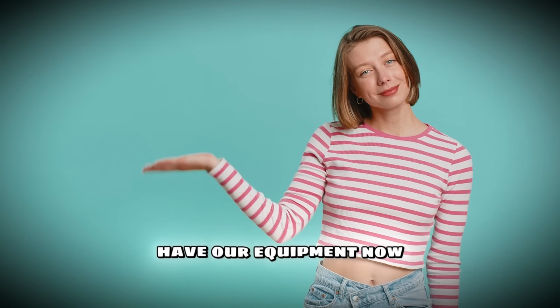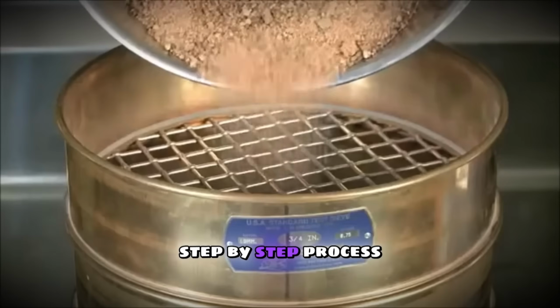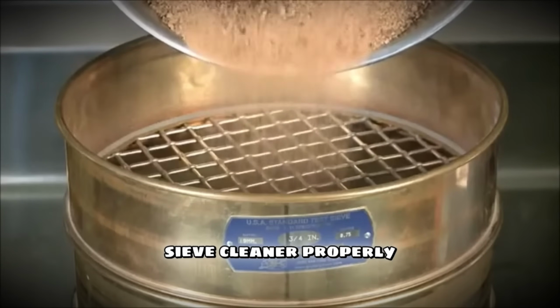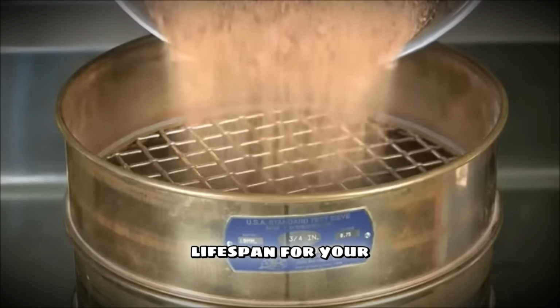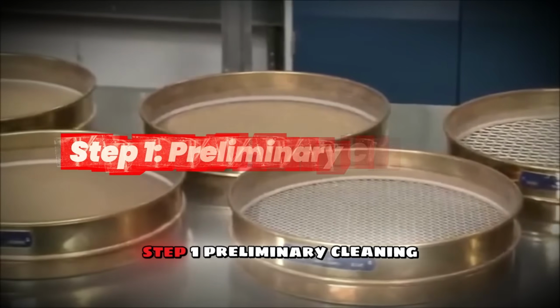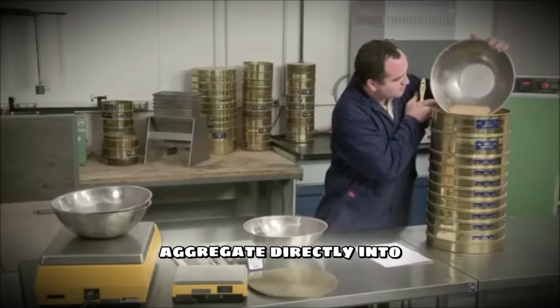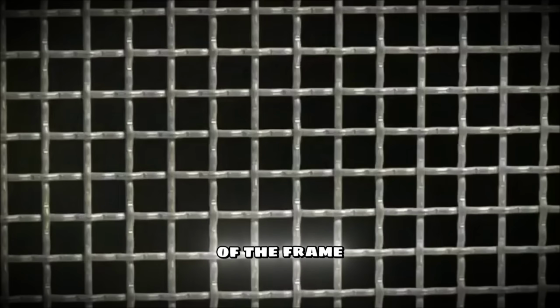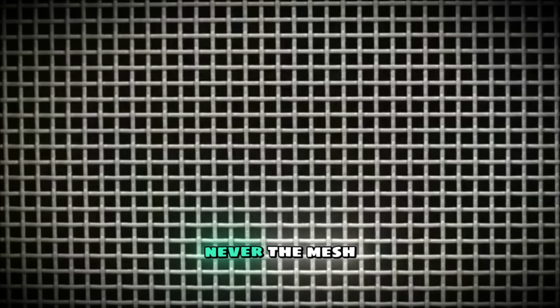All right, we have our equipment. Now let's walk through the exact step-by-step process of how to use an ultrasonic sieve cleaner properly to ensure maximum lifespan for your testing equipment. Step 1. Preliminary cleaning. Never put a sieve full of heavy aggregate directly into the machine. Gently invert the sieve and give it a soft tap on the side of the frame with a wooden brush handle, never the mesh, to remove the bulk of the loose dry material.